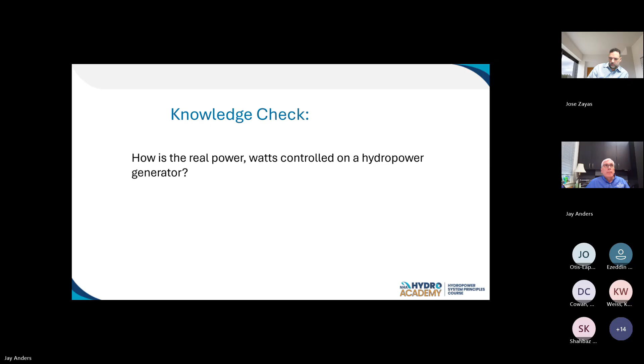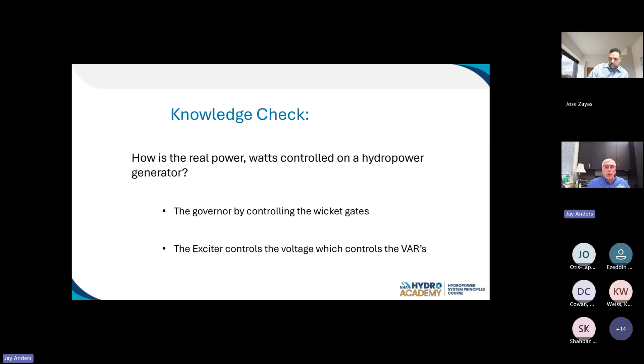We got 2 so far. All right, we're getting some convergence here. The governor. Exactly. And if I were to ask you about voltage control, I've asked you about the imaginary power, of course, you would tell me that would be my excitation system controlling my VARs. So the governor, via the wicket gates, controls watts, real power. And the excitation system, it controls my voltage, which in turn controls the VAR load.